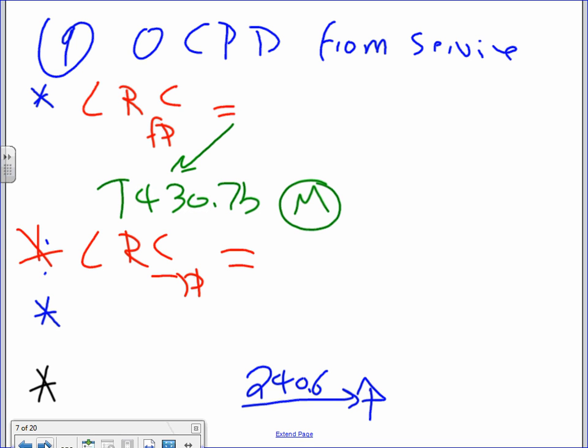This is the fire pump, the fire pump horsepower. We're going to do it for both. Okay, so here we go. So if you guys, what's the multiplier? What was the multiplier for the fire pump? The code letter M. From code letter M and Table 430.7(B) for M, you're going to find the upper limit is 11.19. Multiply it. Derek, what's the horsepower of that one? 50, thank you. Multiply by 1,000 because it's given in thousands.